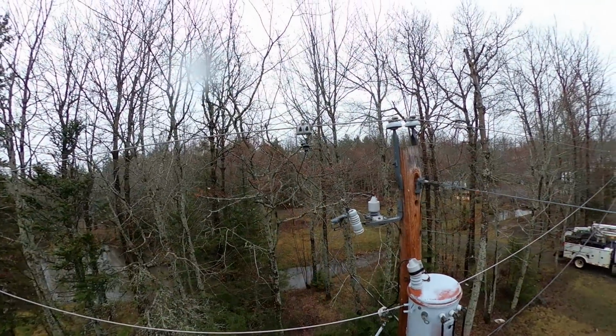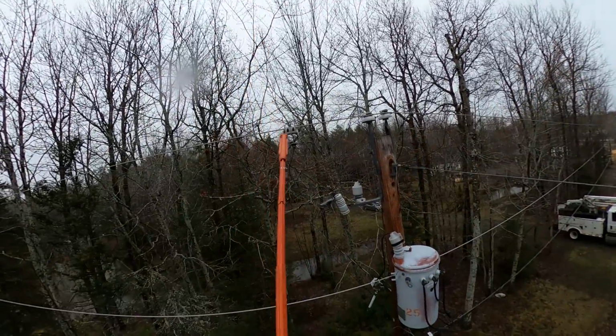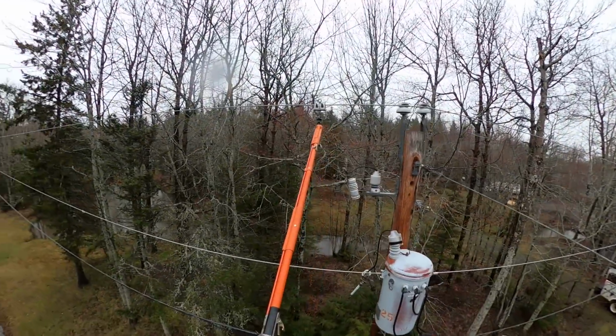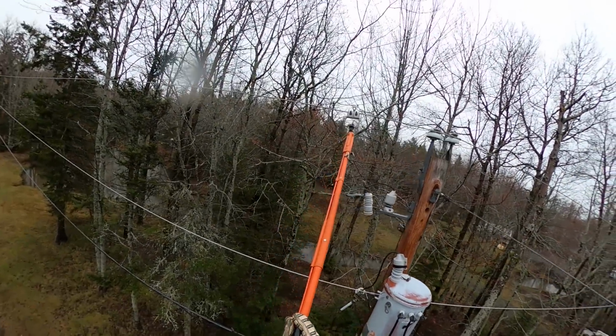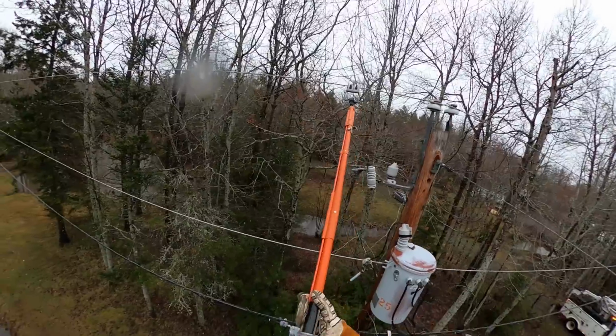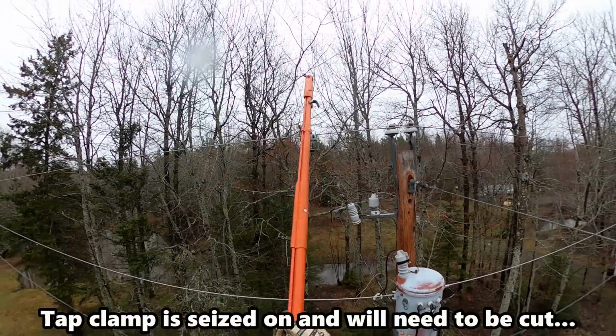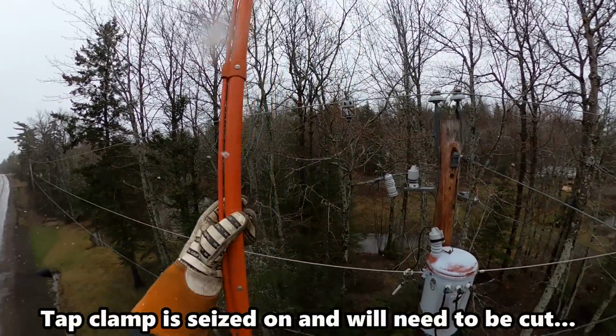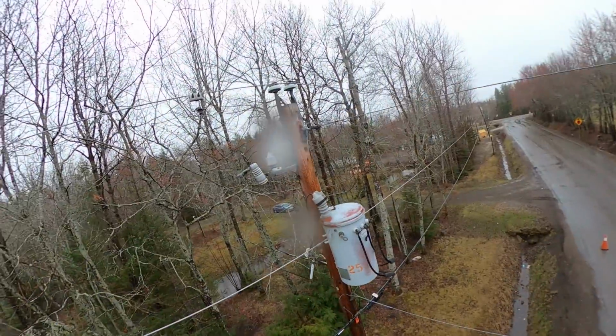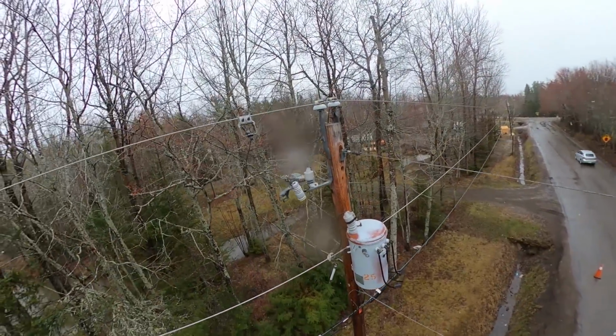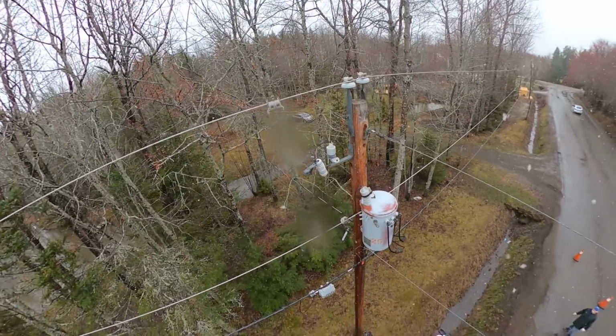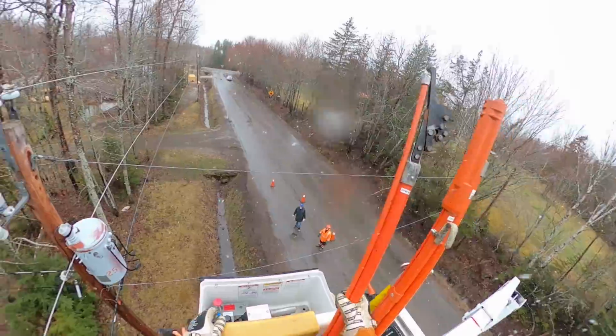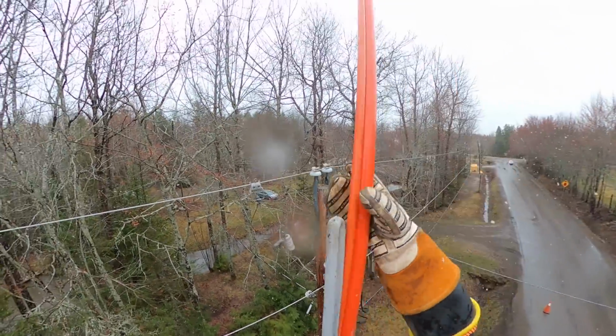One of the first things we're going to do here is clear the hazard where the porcelain is already cracked in the cutout. Before we touch anything, we want to de-energize that cutout, so we're going to use a hot stick to untap it. Now, where it's cracked, sometimes as soon as you disturb that, it could break apart and the rest of it could fall apart. And if that 7200 volt lead touches the bracket, the bottom of the lightning arrestor, or even the pole in some circumstances, we could have a nasty arc flash.